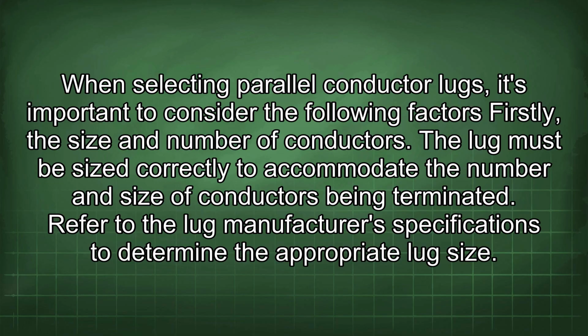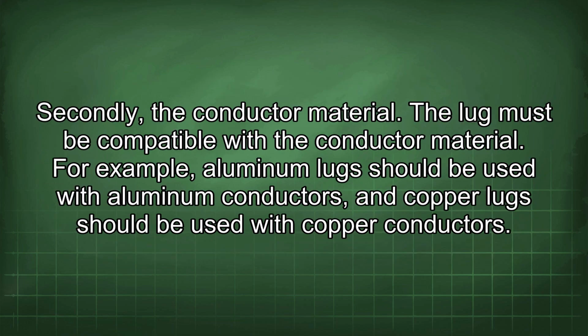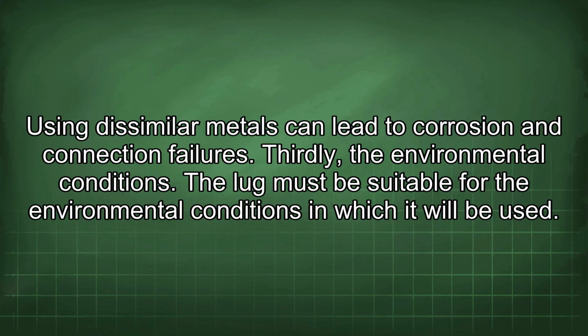Firstly, the size and number of conductors. The lug must be sized correctly to accommodate the number and size of conductors being terminated. Refer to the lug manufacturer's specifications to determine the appropriate lug size. Secondly, the conductor material. The lug must be compatible with the conductor material. For example, aluminum lugs should be used with aluminum conductors, and copper lugs should be used with copper conductors. Using dissimilar metals can lead to corrosion and connection failures.